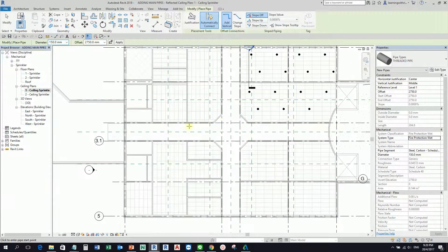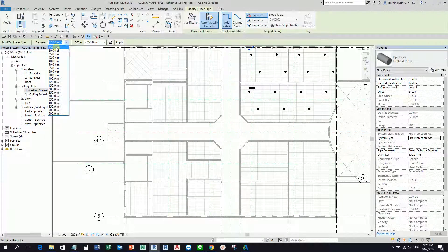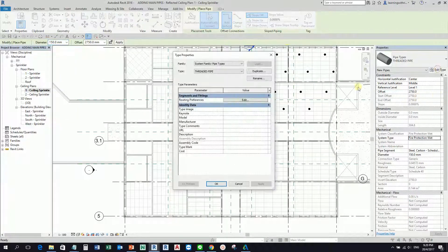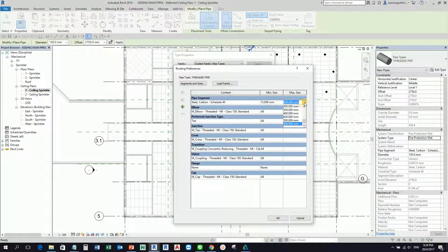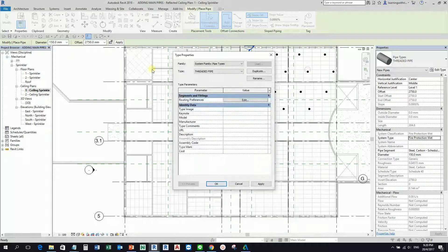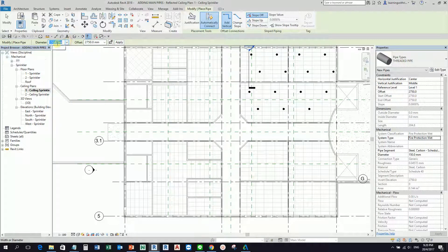For the diameter I'll use 150mm. If you click the drop-down arrow you can see the minimum is 15mm and the maximum is 600mm — that's because we changed it in the routing preferences. If you only want a range of, say, 15mm to 200mm you can set 200 as the maximum size, and then only those sizes will appear in the drop-down.